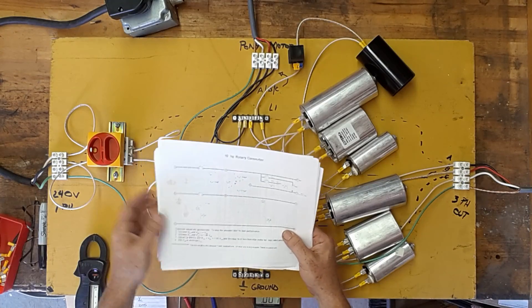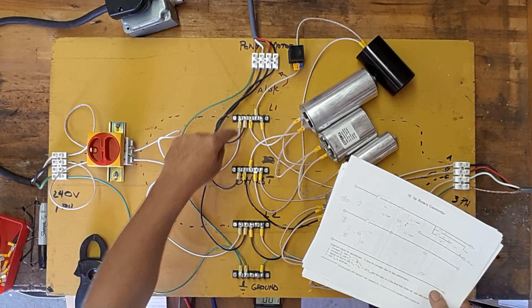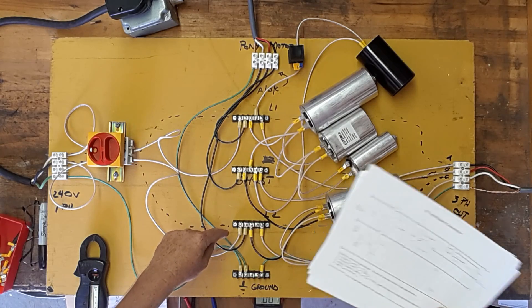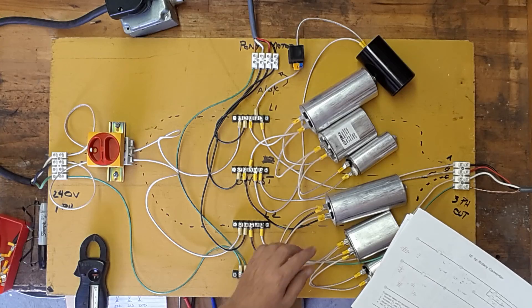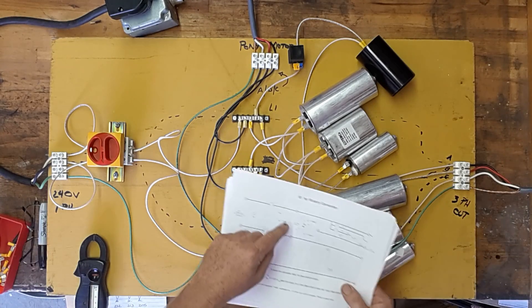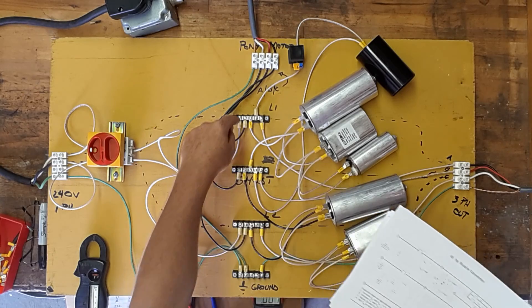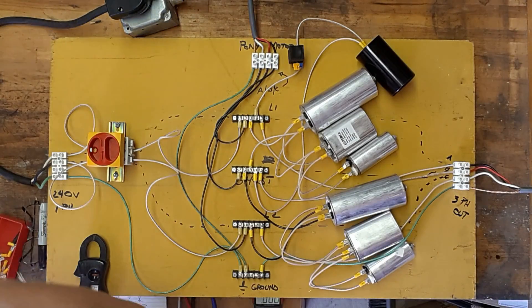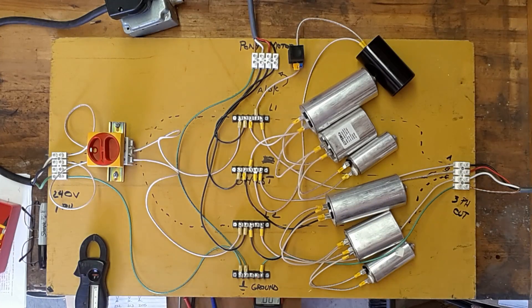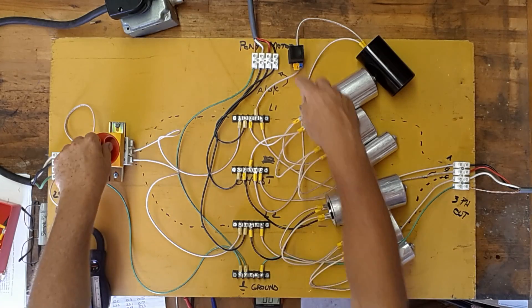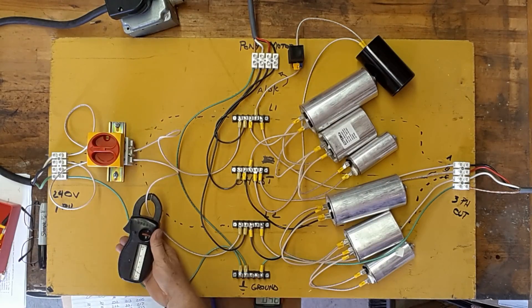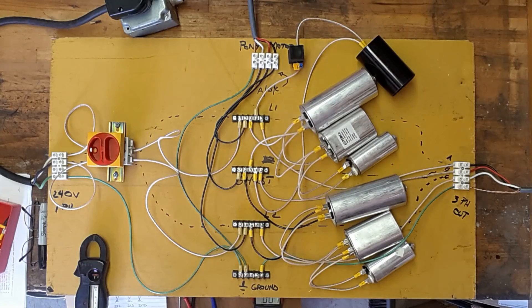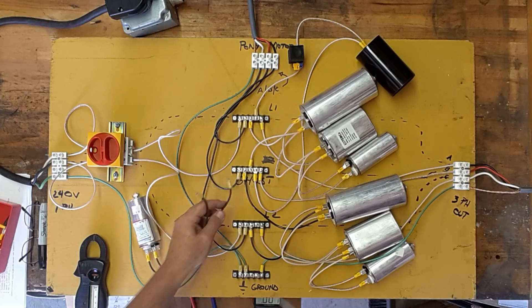With it idling, we're getting these readings. The last thing we're going to do is this capacitor across here, so that's from here to here. Now I could do that from here to here, but again for this open view, this capacitor is from here to here, and this reduces amperage, so we're no longer checking volts, we're checking amps. The first thing we're going to do is get a baseline, so with it running. This is a 20 microfarad capacitor.